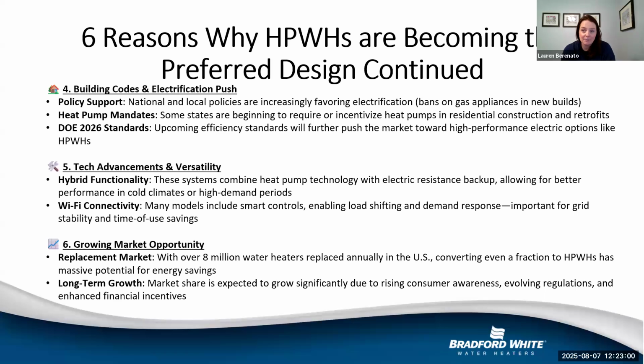Certain high efficiency gas models need to be completely updated, because their thermal efficiency needs to be higher to meet that 95% threshold. The good thing about these standards is that they come into effect on date of manufacture, October 6th. It's not date of install and it is not date of specification. So as long as the product has been manufactured before October 6th of 2026, it can be installed on a project.